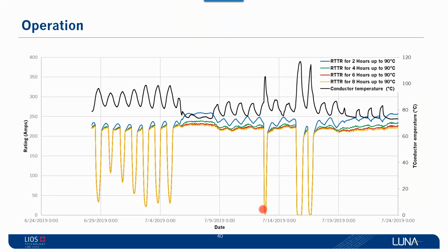This is the time, number of days in July, and this is the cable rating, the capacity rating on the cable. And on the right is the conductor temperature. So what that simply means is that for your conductor temperature, we want to make sure that it stays below 90. And for that to happen, the operators have to realize that they have to keep operating the line at mostly below 250 amp. And I will show that quickly in the next slide.